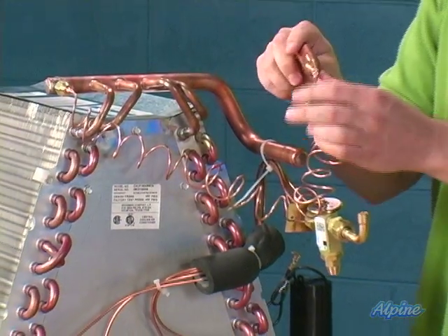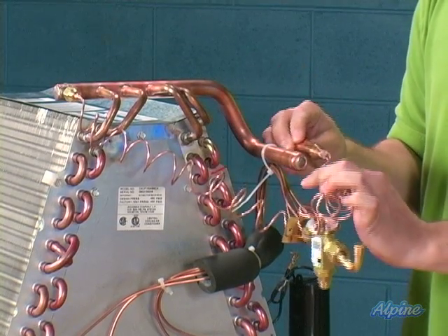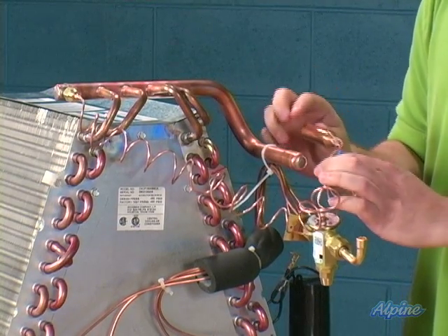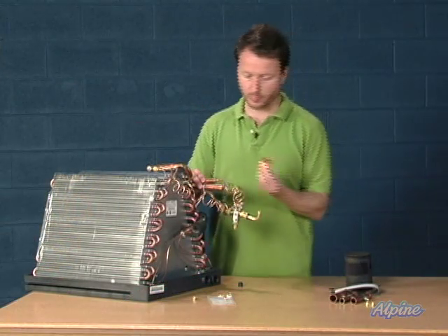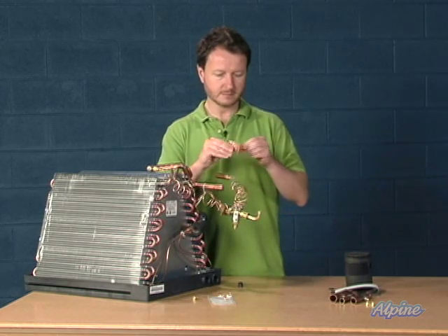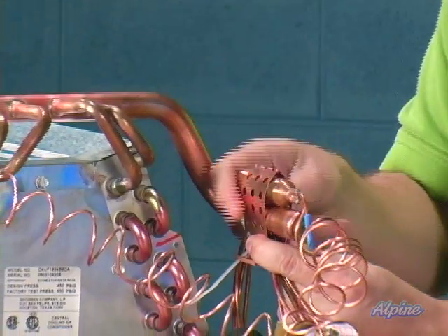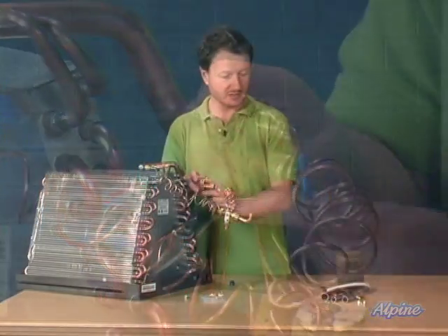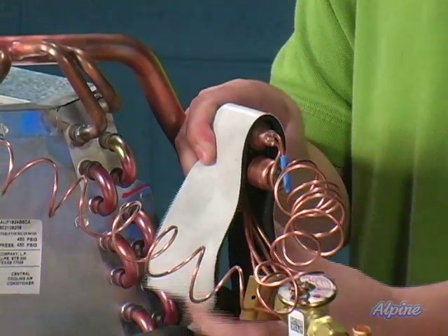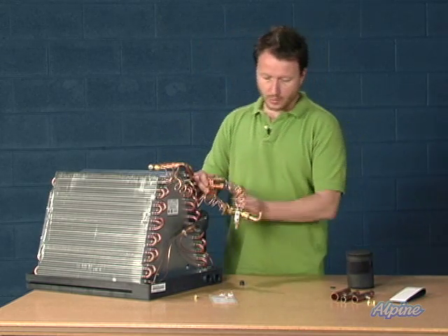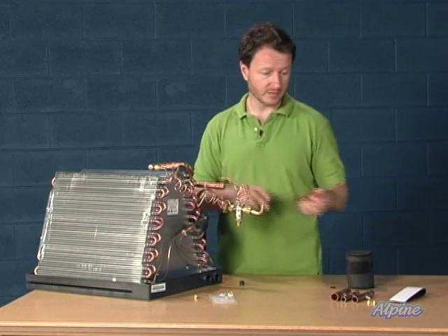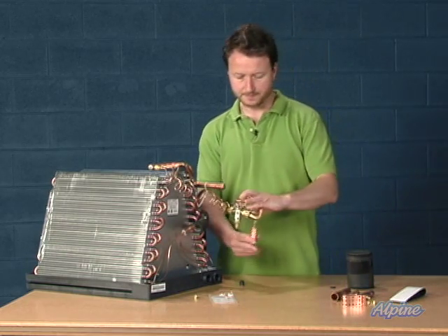And then this thing here is a sensing bulb, and this is what senses the temperature of the refrigerant. So the way it's going to do that is by simply strapping it on to this pipe and then holding it in place with whatever brackets are provided, like so. Bracket will be put in place. It comes with some nuts and bolts to secure that. Once it's in place, it also comes with some insulation. The insulation will be wrapped around here, and that way it will sense the temperature of just the pipe and not the ambient air around it. And really, it's simple as that. It's not going to be too big of a deal.